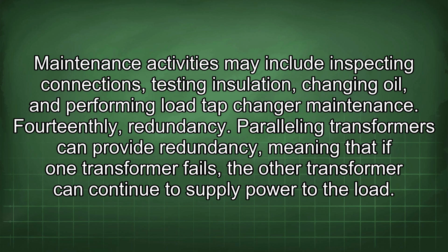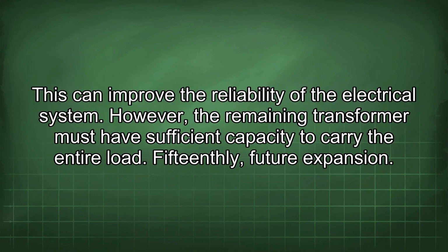Fourteenthly, redundancy. Paralleling transformers can provide redundancy, meaning that if one transformer fails, the other transformer can continue to supply power to the load. This can improve the reliability of the electrical system. However, the remaining transformer must have sufficient capacity to carry the entire load.